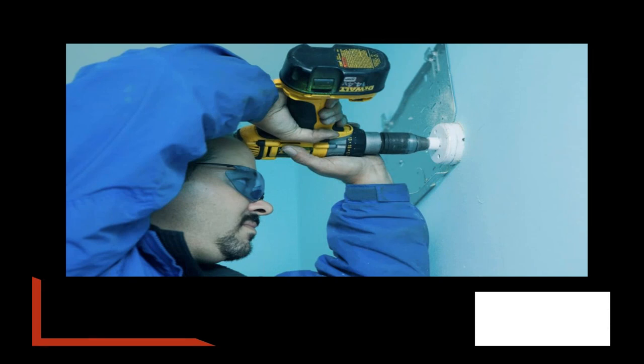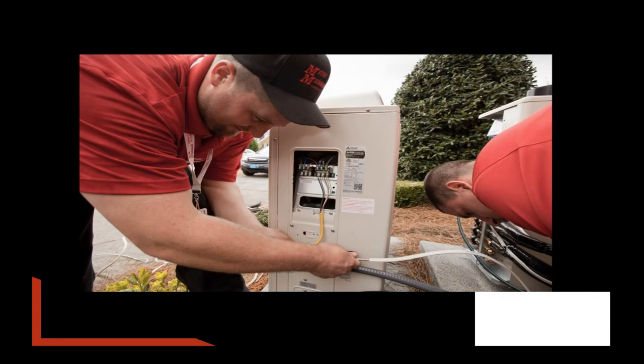So you probably need to put some sort of a mastic or aluminum coating that would prevent anything from coming through, in addition to spray foam to maintain the insulation level in and around the tubing. Next slide. Of course, following code is an important part of a quality installation. Selecting the right electrical equipment, having an electrician perform the appropriate duties throughout the entire process, pulling the correct permits. Next slide.